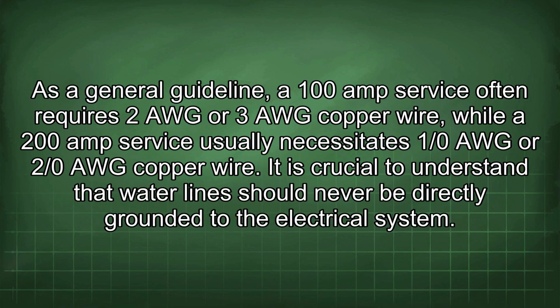As a general guideline, a 100 amp service often requires 2 AWG or 3 AWG copper wire, while a 200 amp service usually necessitates 1/0 AWG or 2/0 AWG copper wire.